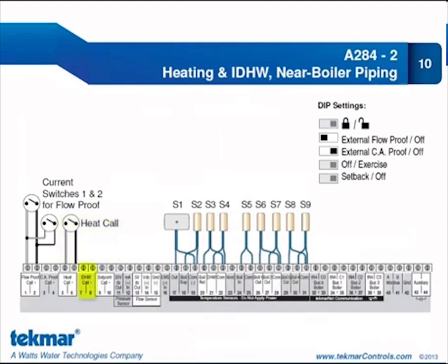We do not have an indirect domestic hot water call terminal here, because again, just like in the first application, we are controlling the indirect domestic hot water with a domestic hot water sensor, so we'll leave those terminals blank. Coming to our sensors, we have our outdoor sensor to provide outdoor temperature reset to the space heating load, and we have our indirect domestic hot water sensor, boiler supply, boiler return, boiler inlet, and individual boiler outlet sensors.